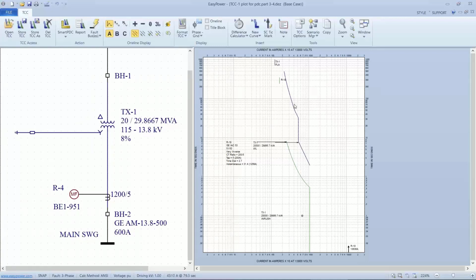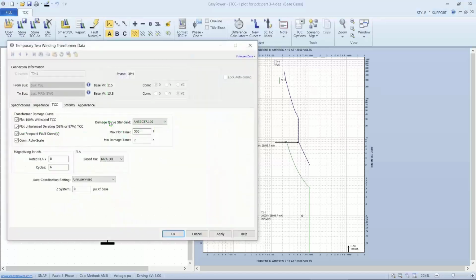So this looks a little bit different from what the transformers we started out talking about in week 1. If I open up the dialog box, under the TCC tab for the two-winding transformer data dialog box, I see 4 default check marks. So let's talk briefly about what each of these are about. If I apply, it takes away my TCC curve. First of all, we're going to plot the 100% damage curve.